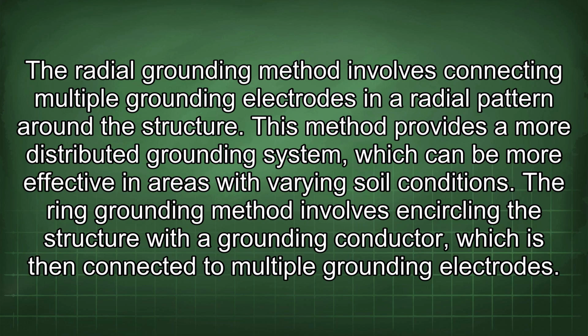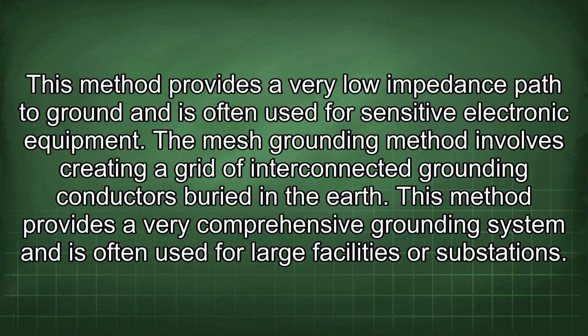The radial grounding method involves connecting multiple grounding electrodes in a radial pattern around the structure. This method provides a more distributed grounding system which can be more effective in areas with varying soil conditions. The ring grounding method involves encircling the structure with a grounding conductor, which is then connected to multiple grounding electrodes. This method provides a very low impedance path to ground and is often used for sensitive electronic equipment. The mesh grounding method involves creating a grid of interconnected grounding conductors buried in the earth. This method provides a very comprehensive grounding system and is often used for large facilities or substations.